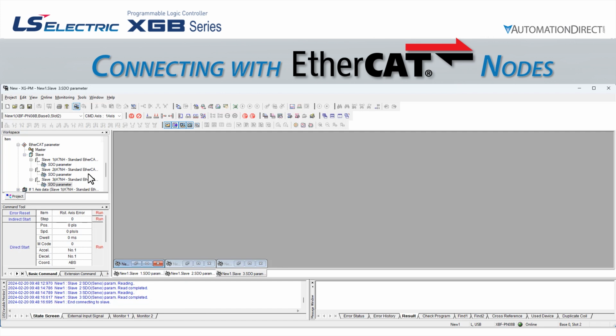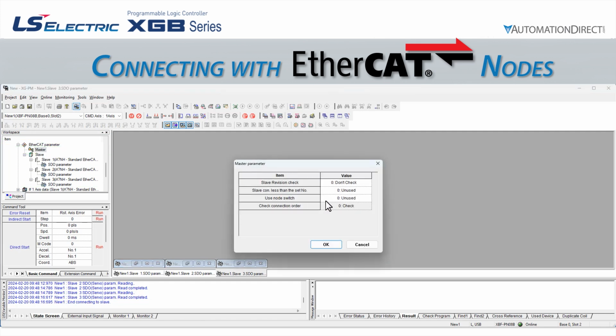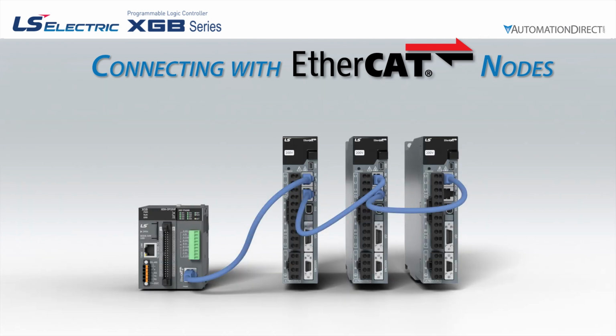To enable this option, we will go to the project window on the left side and double-click on Master. We will then set the Use Node Switch value to 1, Used.